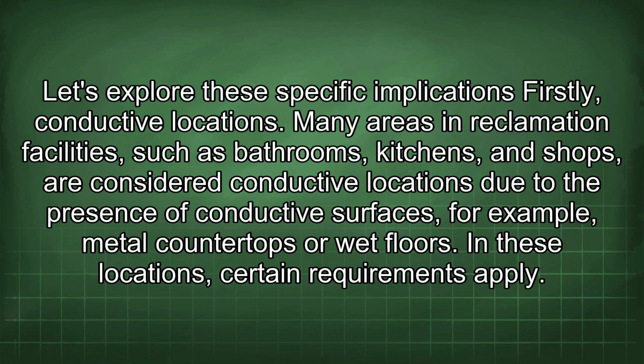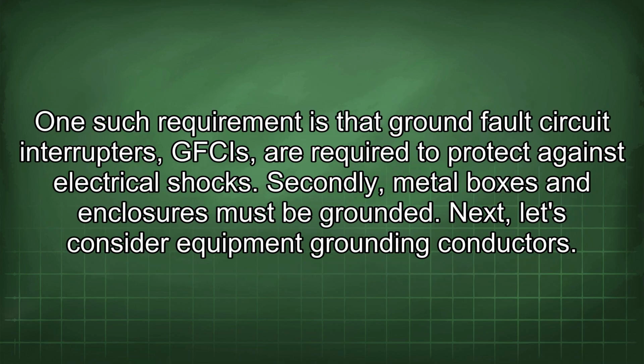Firstly, conductive locations. Many areas in reclamation facilities, such as bathrooms, kitchens, and shops, are considered conductive locations due to the presence of conductive surfaces, for example, metal countertops or wet floors. In these locations, certain requirements apply. One such requirement is that ground fault circuit interrupters, GFCIs, are required to protect against electrical shocks. Secondly, metal boxes and enclosures must be grounded.